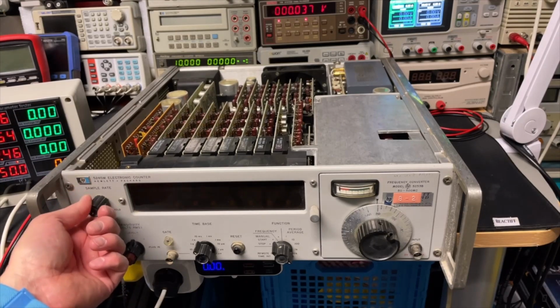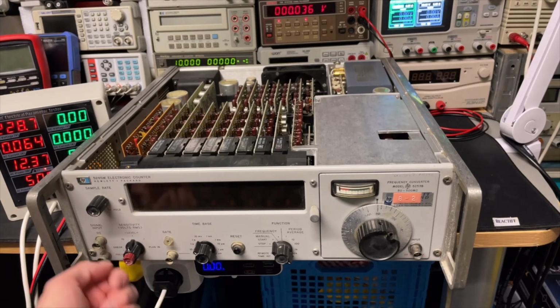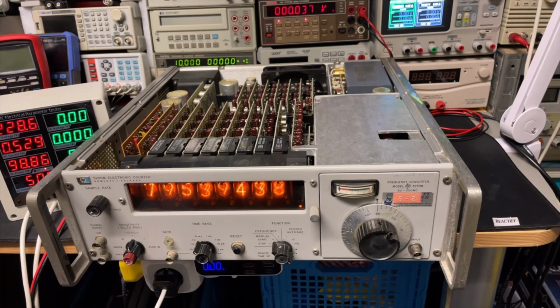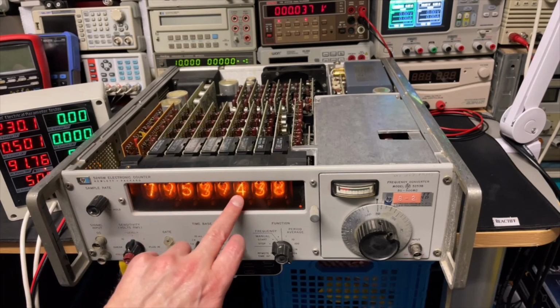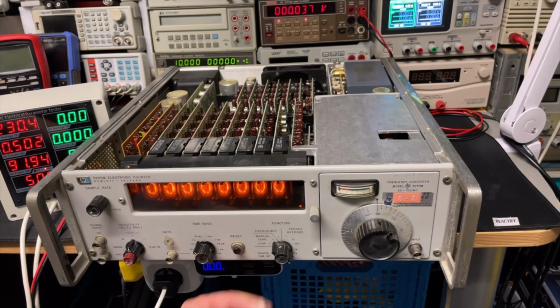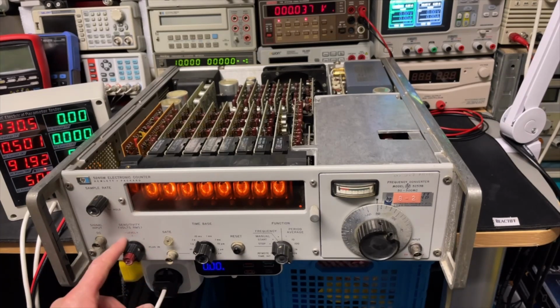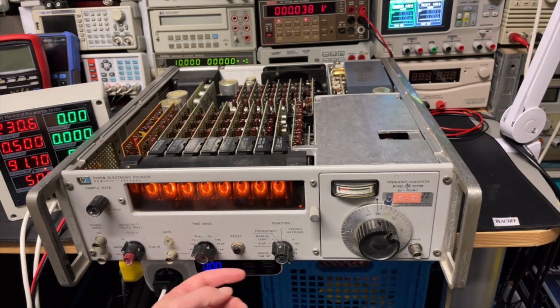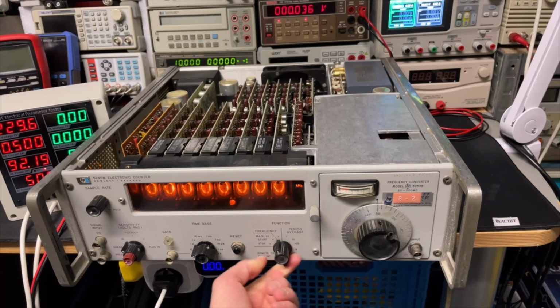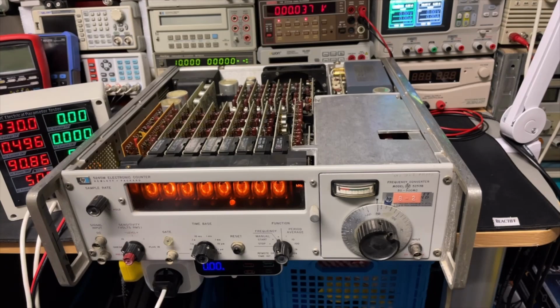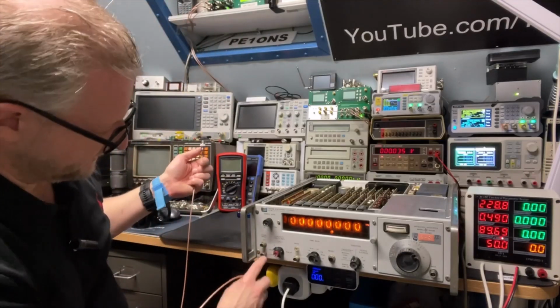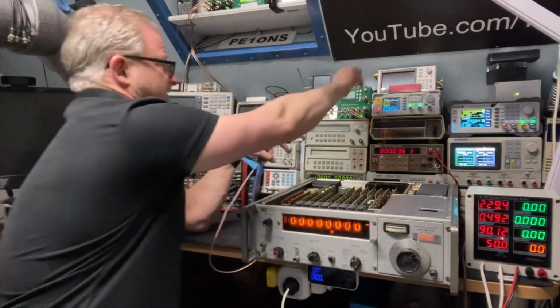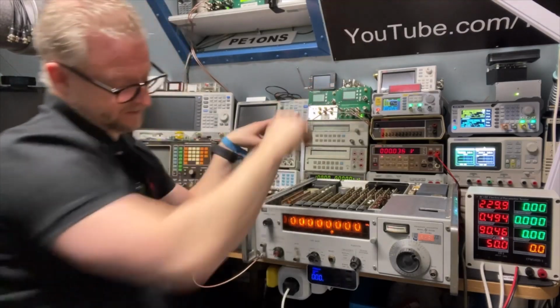Okay, let's just power it on. We can have a look here at the power also. Big ventilator running. Oof, a lot of noise. And we do see 1, 2, 3, 4, 5, 6, 7, 8 digits. That is good. And 100 watts, and it will stay more or less there. Let's try an input of 10 volts, highest first. One second. Let's put in the frequency, 10 megahertz, and let's see. Okay, let's put 10 megahertz in the input, the AC, and I just take it from one of my distribution amplifiers.